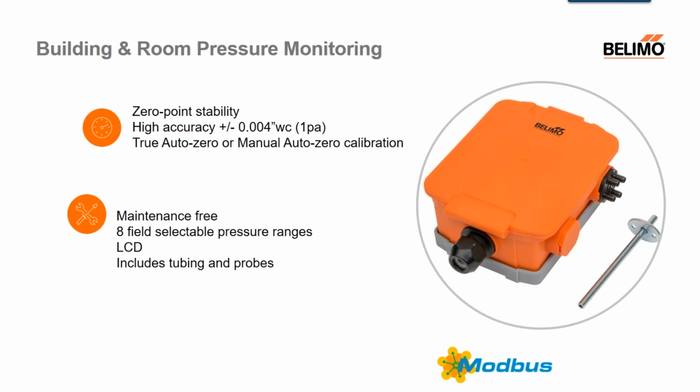The 22DP pressure sensors are calibrated and tested during and after the production process, and all accuracy stated are the total error band. This is the typical tolerance, including repeatability and temperature dependence tolerance, and is not the sensing element component accuracy.